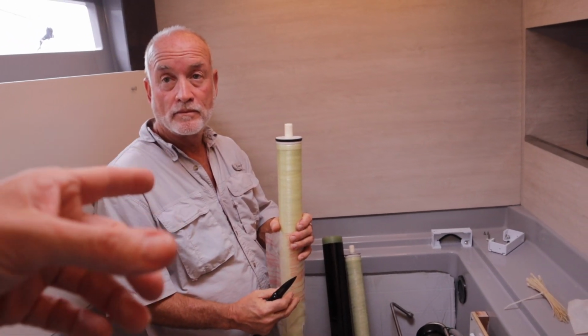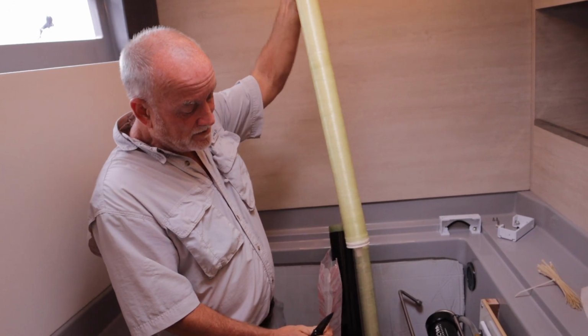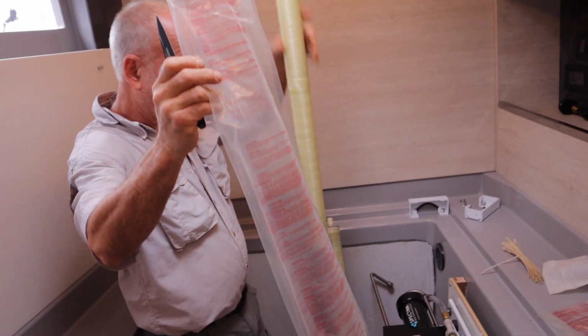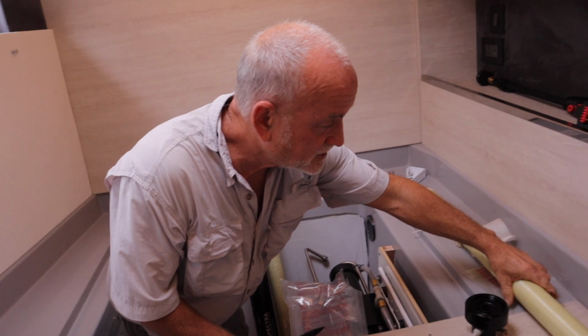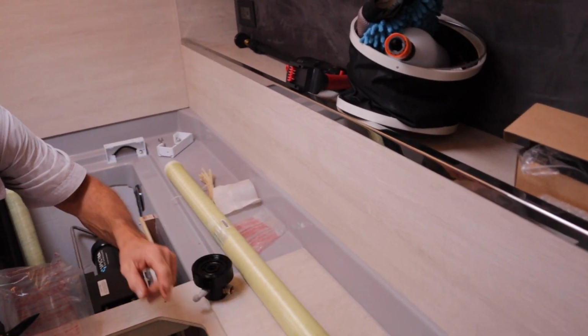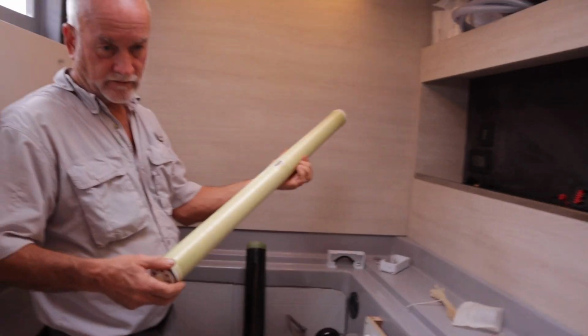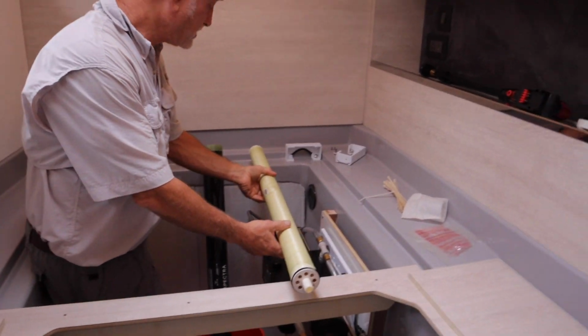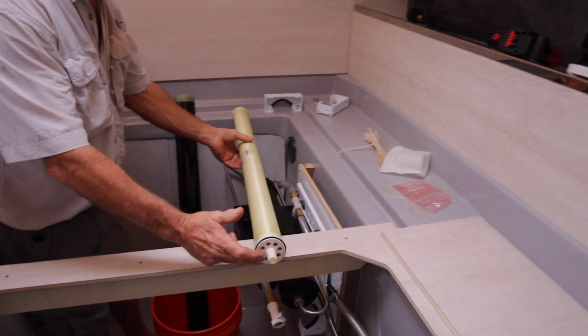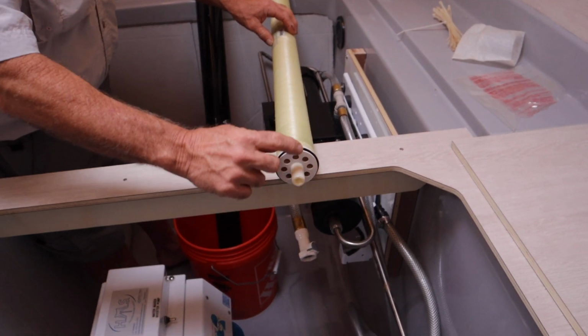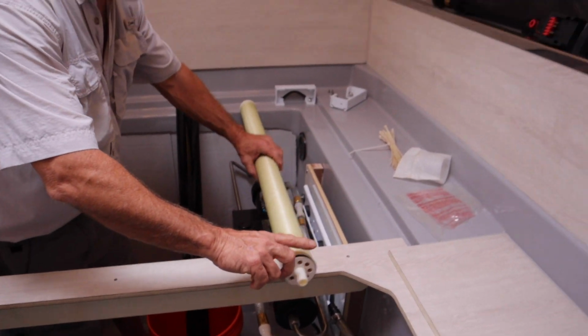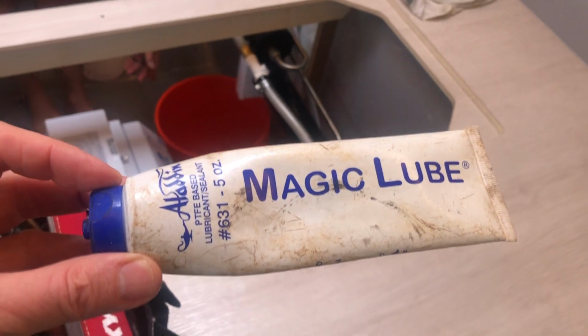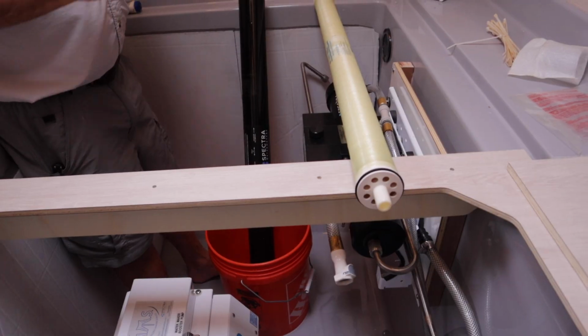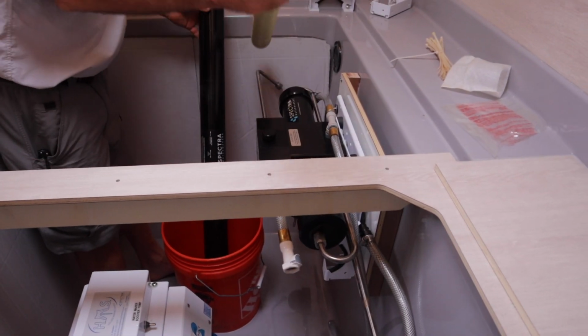Obviously, it is orientated. It is. The membrane itself doesn't care what direction it's in. If you notice on this end, it looks like it's an O-ring, but there's not one at that end. What we do is put just a little bit of silicone grease, water-based silicone grease, on this product tube and a little bit just on the brine sealing. We just shine it. We don't load it. Don't load it up.